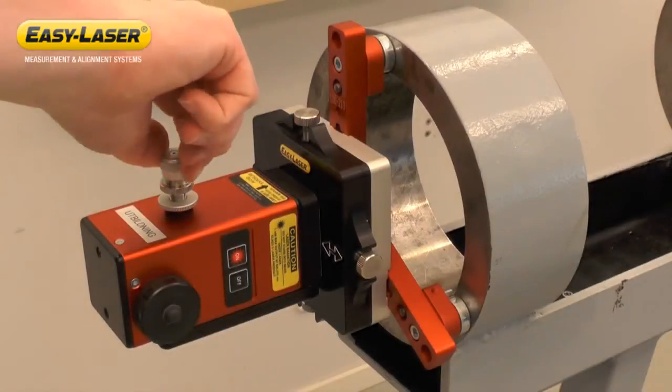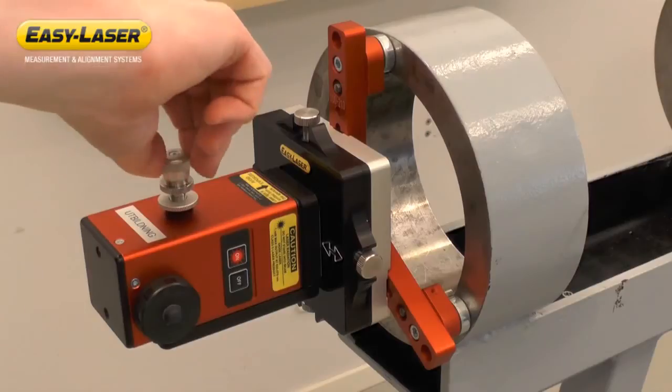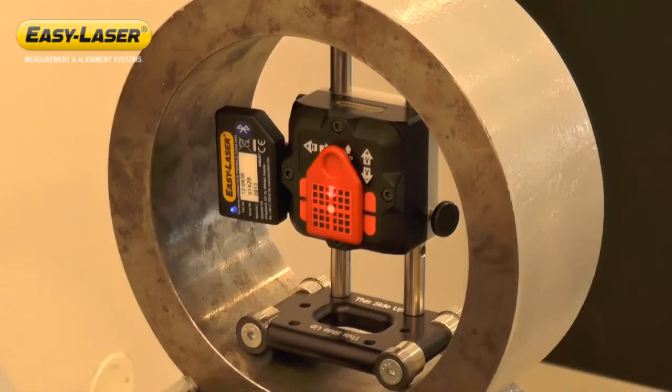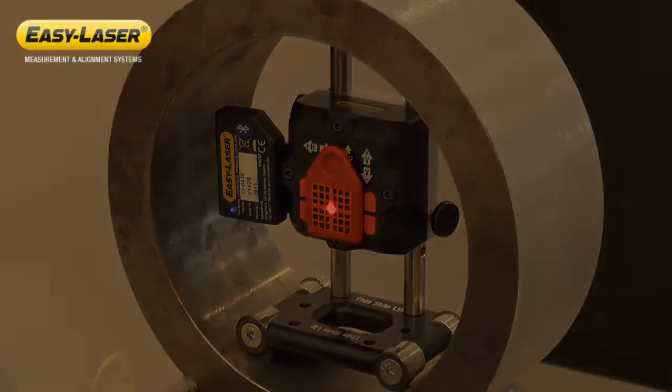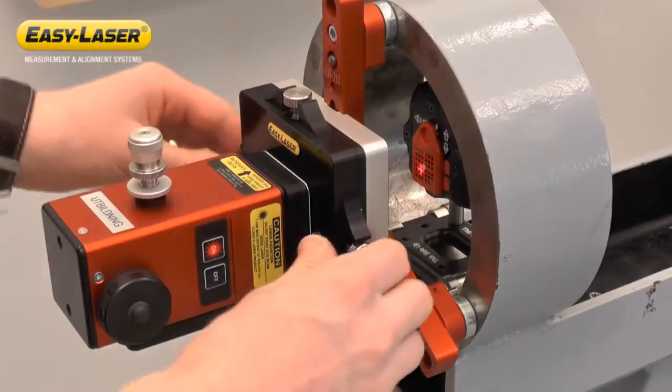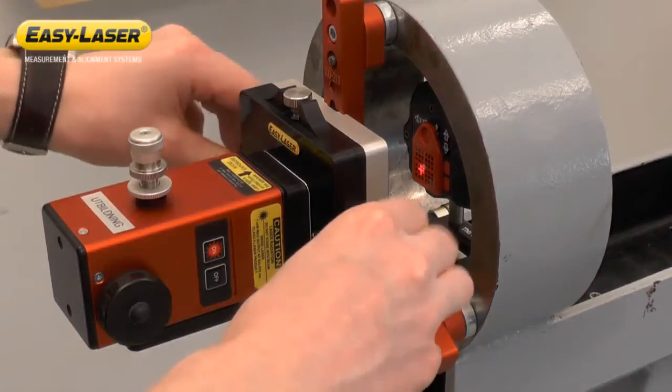First I have to align the laser beam along the measurement. I do this through adjustment of the tilt table while looking at the target on the detector placed in the bearing journal the farthest away. Then using the offset screws we adjust the offset of the laser transmitter close to the laser.